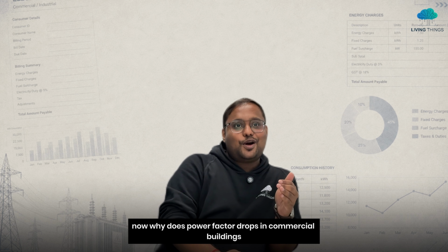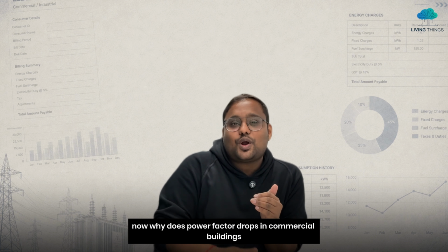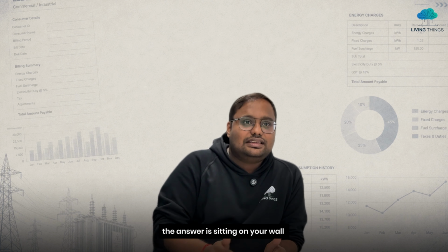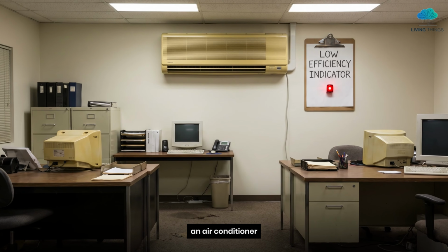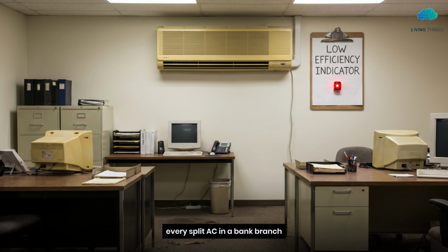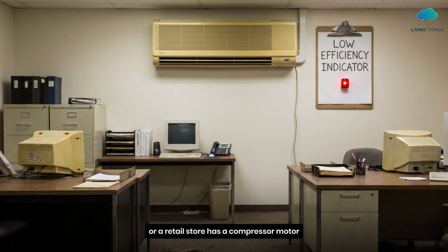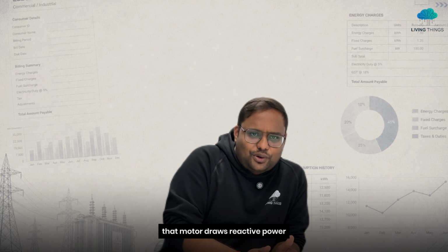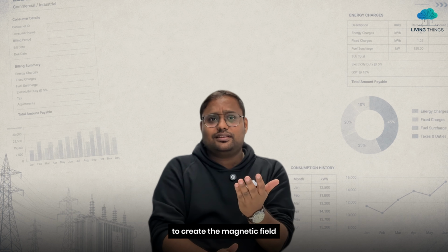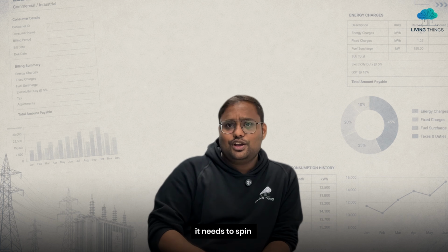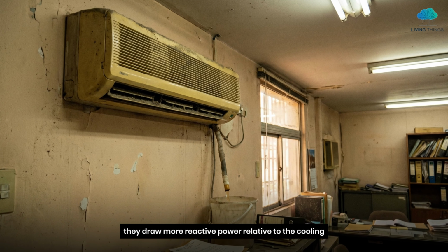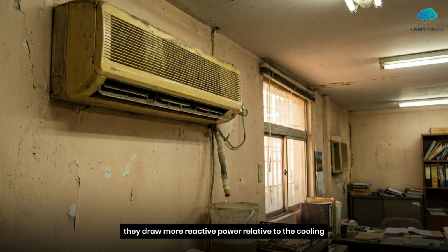Okay, now why does power factor drop in commercial buildings? The answer is sitting on your wall: an air conditioner. Every split AC in a bank branch or a retail store has a compressor motor. That motor draws reactive power to create the magnetic field it needs to spin. Older ACs are worse. They draw more reactive power relative to the cooling they produce.